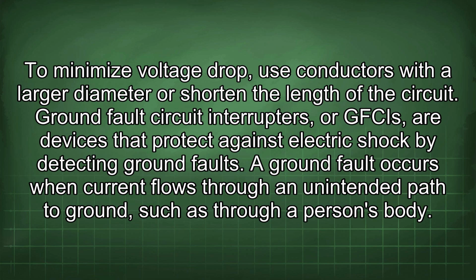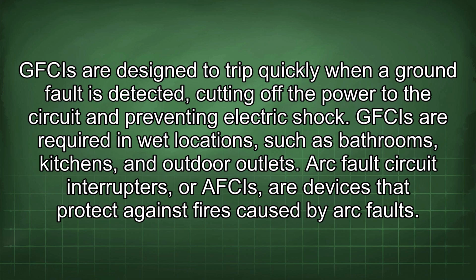Ground fault circuit interrupters, or GFCIs, are devices that protect against electric shock by detecting ground faults. A ground fault occurs when current flows through an unintended path to ground, such as through a person's body. GFCIs are designed to trip quickly when a ground fault is detected, cutting off the power to the circuit and preventing electric shock. GFCIs are required in wet locations, such as bathrooms, kitchens, and outdoor outlets.